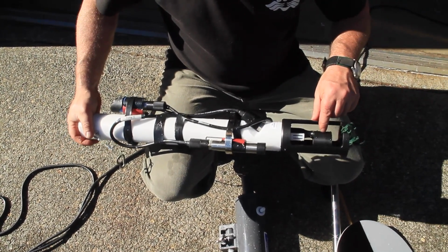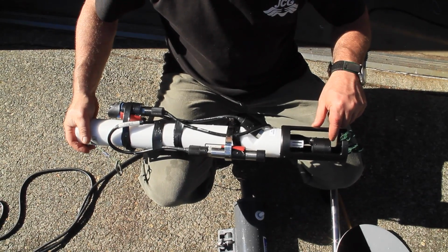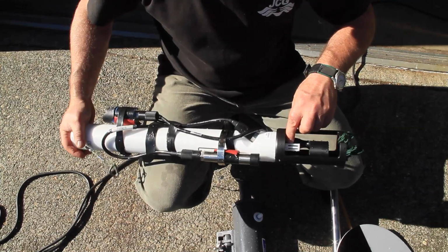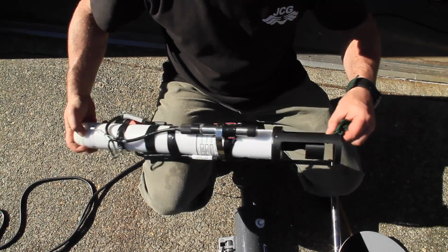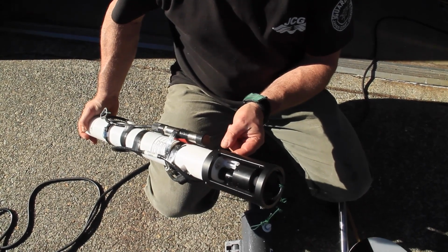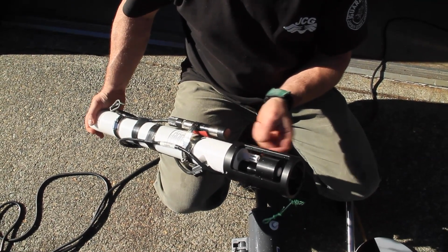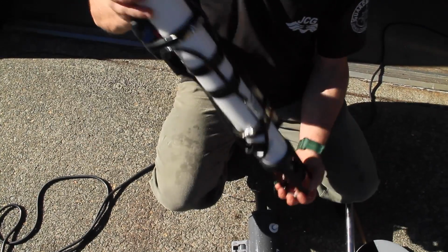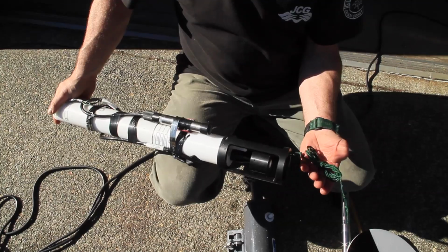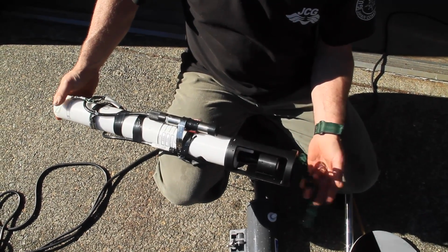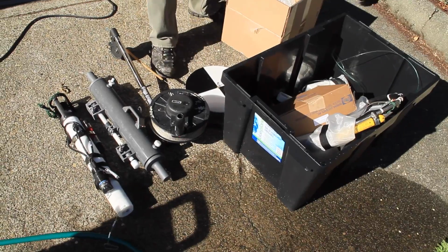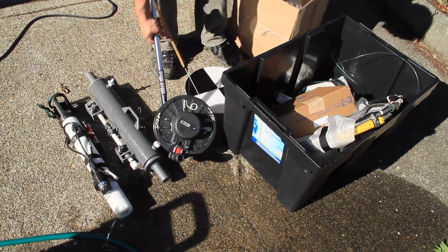This guy here is the conductivity sensor, measures the salinity of the seawater. This is the thermistor that measures the temperature. The skinny little needle is the actual sensor. It's very quick. This is the port for the pressure sensor. It should be clean and should be able to drip water out of it. And you should always shake it out a little bit and make sure that the water comes out. Make sure your bottom line is all tied up so it doesn't catch on anything. And it's all ready to go for the next time. Okay. I'll put this guy in here.